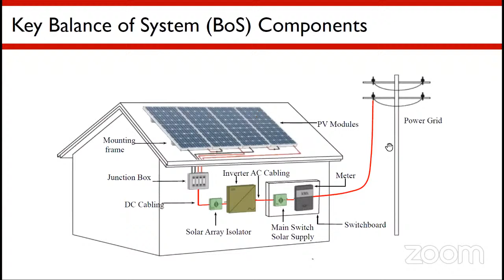The DC cable and AC cable are the cables interconnecting the entire system. One should use the proper cable for the correct application. You should not use an AC cable for DC application, and you should not use a DC cable for AC application. Whatever cables, MCBs, or SPDs you are using, everything should be rated correctly. DC has a separate fuse, DC has a separate MCB, DC has a separate SPD (surge protection device), DC has a separate cable, and DC has a separate indicator. Everything is different - you should never use the same thing for both.